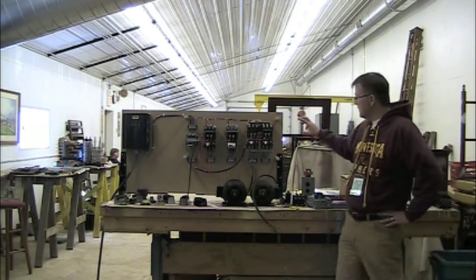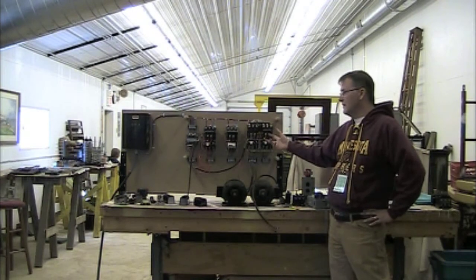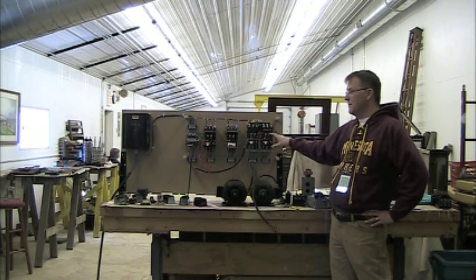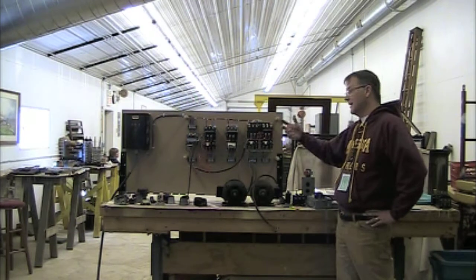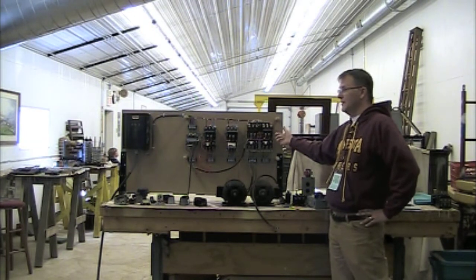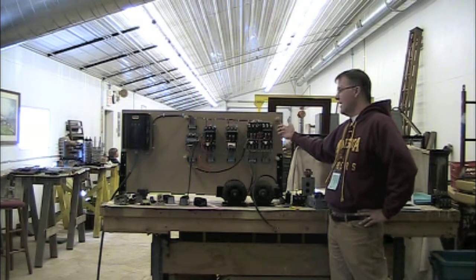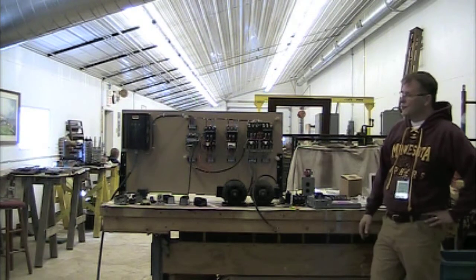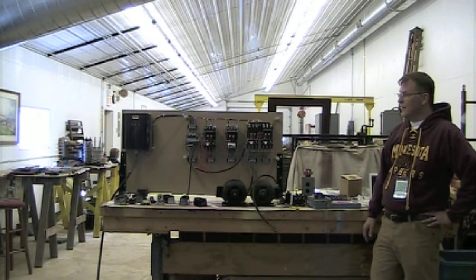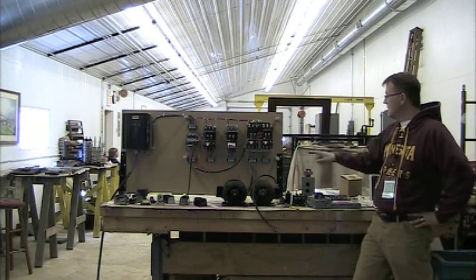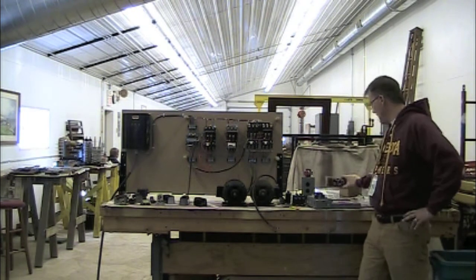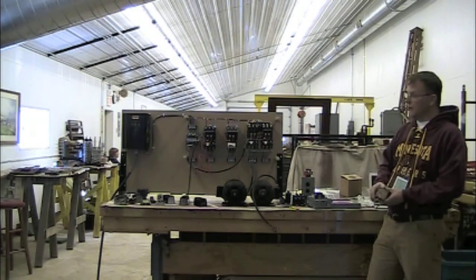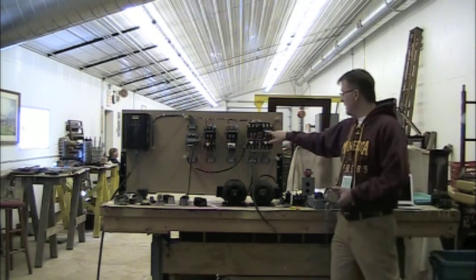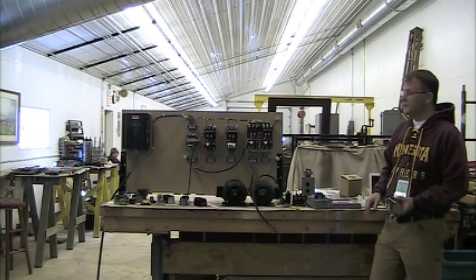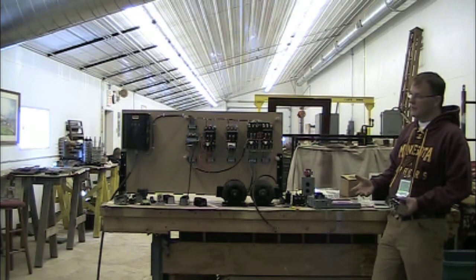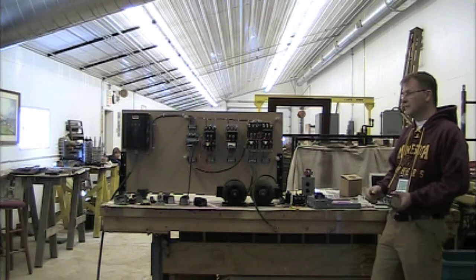Because there's an electrical component of the interlock, and there's mechanical. Because like I said, if it didn't have this mechanical interlock, I could go in and trip that other winding while the other one was energized. So that's why you have the normally open and normally closed buttons and the extra sets of contacts, so that there's an electrical component to that lockout as well as the mechanical.